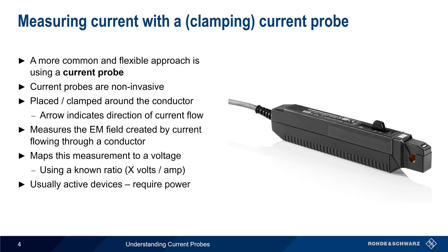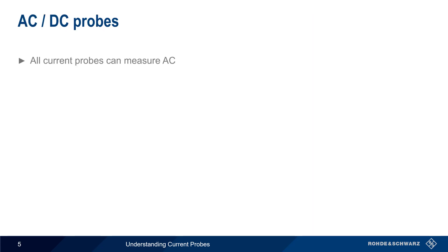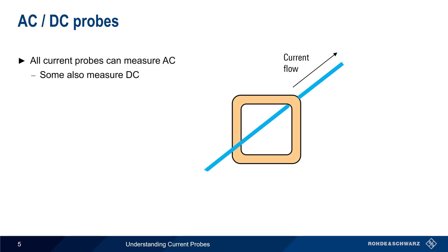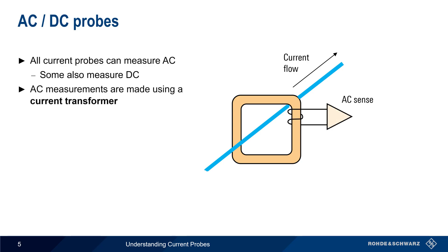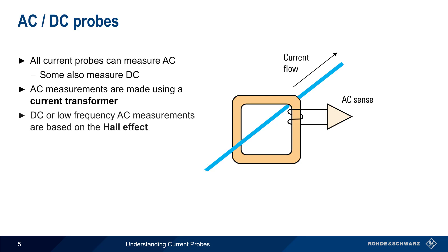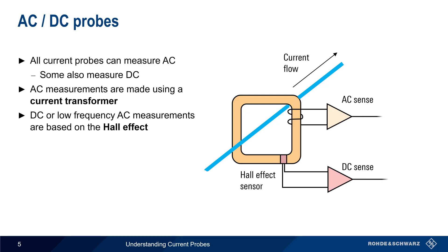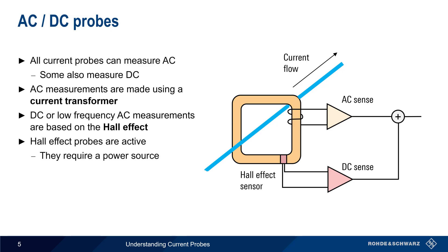Almost all current probes are active devices — that is, they require power to operate. All current probes can detect and measure AC, but some are also able to measure DC currents as well. Different mechanisms are used for each type of measurement. AC current measurements are made using a current transformer, whereas DC or very low-frequency AC current measurements are made using something called a Hall effect sensor. Probes that measure down to DC use a combination of these two methods. Note that Hall effect probes are active, and thus AC-DC probes are usually active as well.